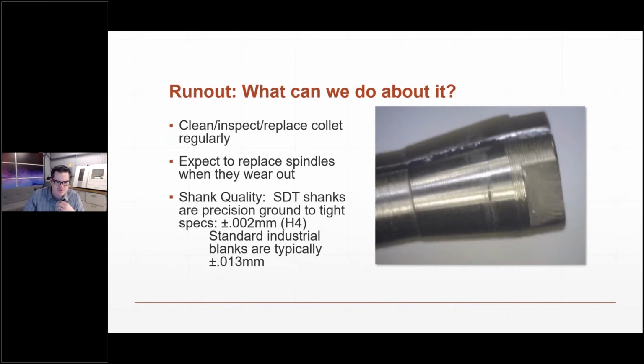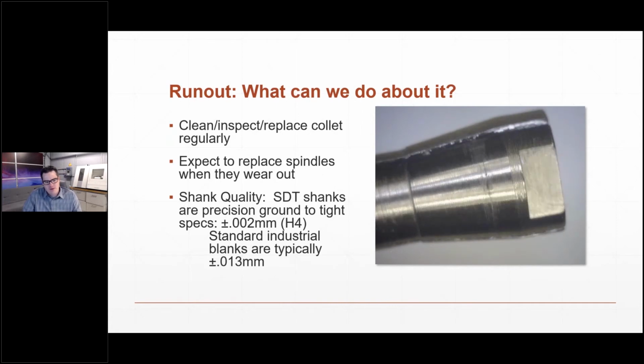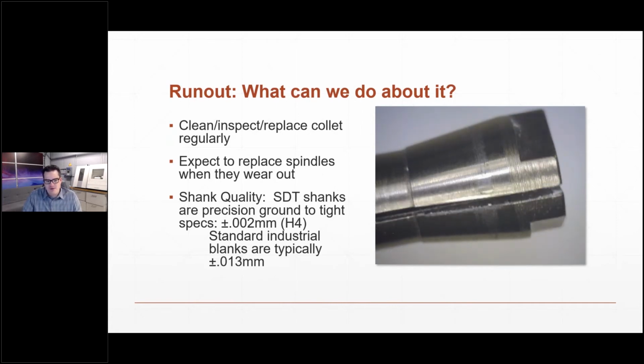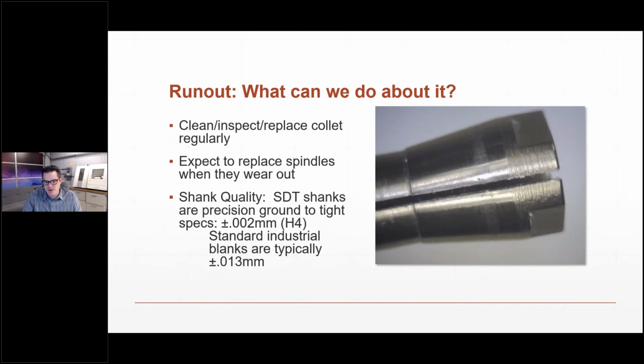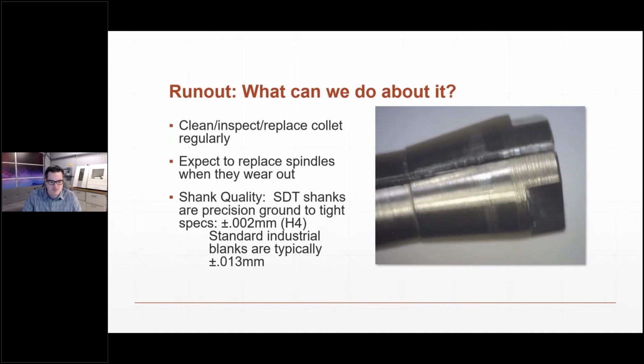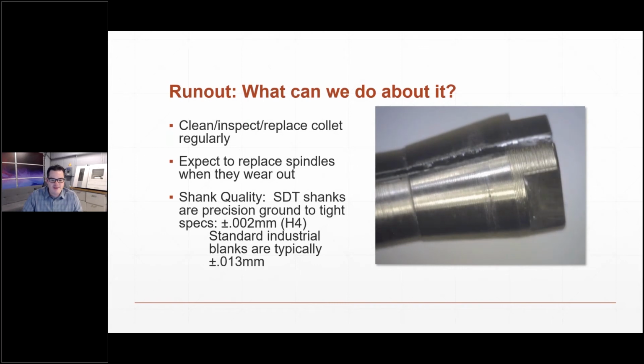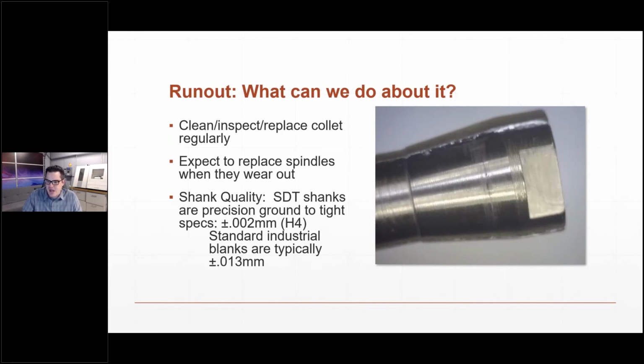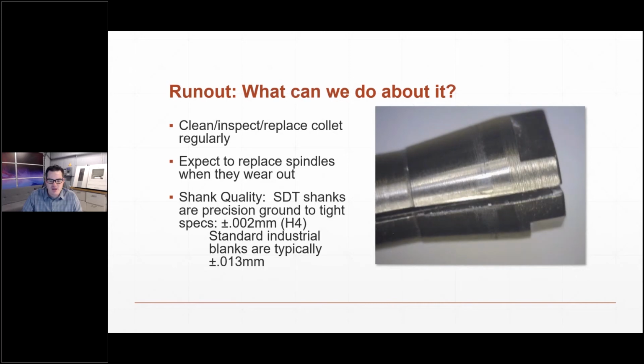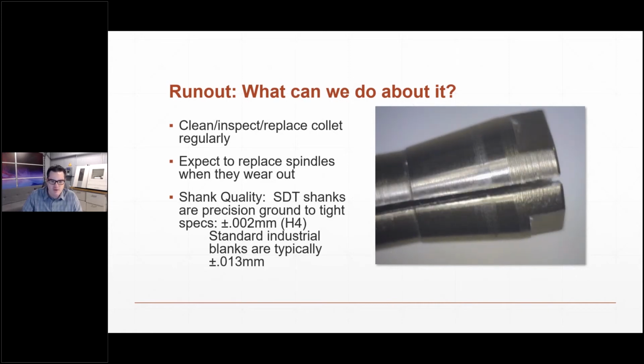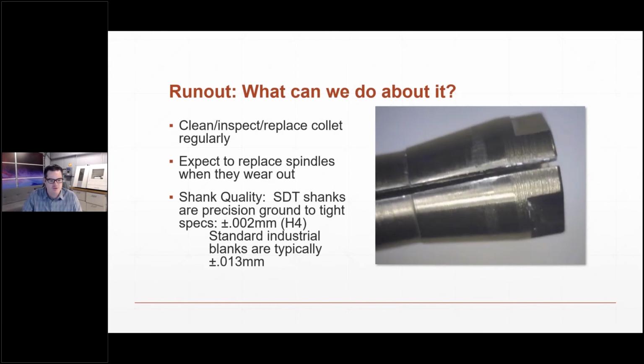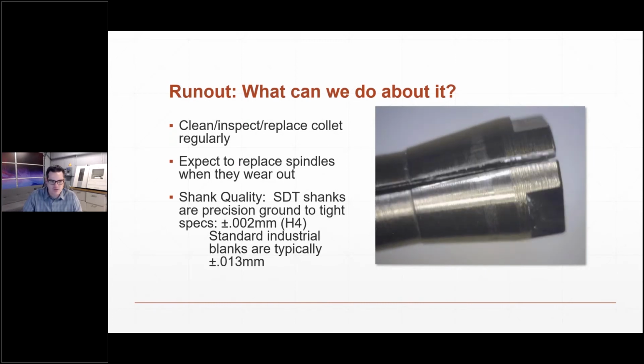The next thing, which we can't directly control as a laboratory but it helps to be aware of, is the spindle itself. It's a high precision instrument, usually running loaded under something like 25,000 to 30,000 RPM - some of the crazy ones go up to 60,000 RPM - and there's a lot of wear and tear on the bearings inside that spindle. Most spindles will have a published hour rating, and you need to be aware that they wear out and you will have to replace it eventually. So if you've done the collet but you've got a lot of hours on the spindle and you're still getting unsatisfactory results, it might be time to do a spindle.